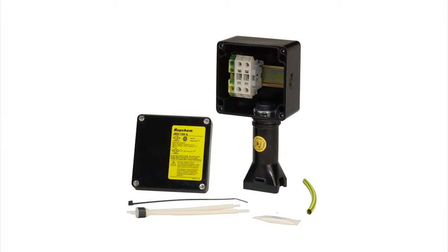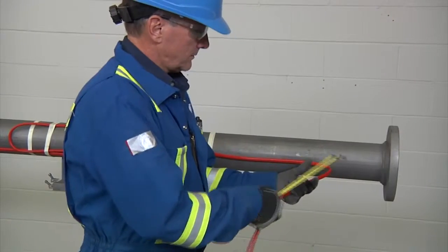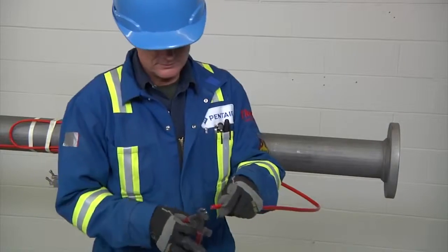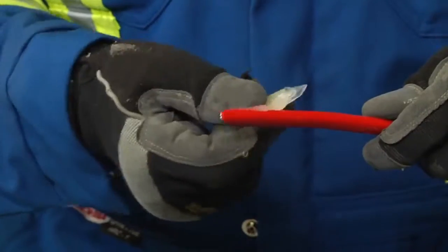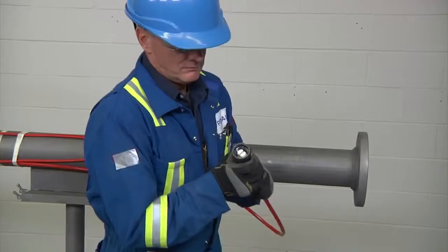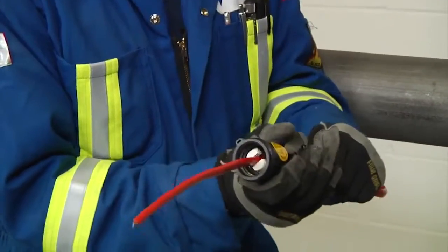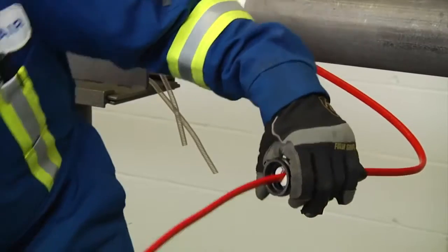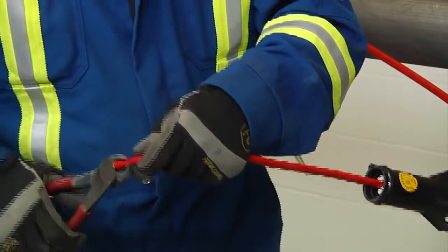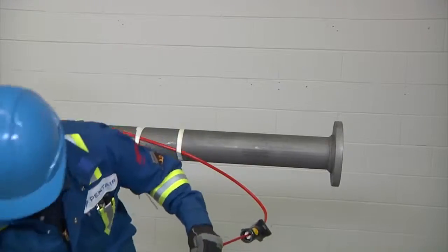The Raychem JBS-100-A is a power connection kit for a single heat tracing cable. First, allow about 24 inches (600 millimeters) of heating cable for installation. Cut the heating cable end at about 45 degrees. Apply lubricant for easier insertion into the stand. Push 18 inches (450 millimeters) of heating cable through the stand.